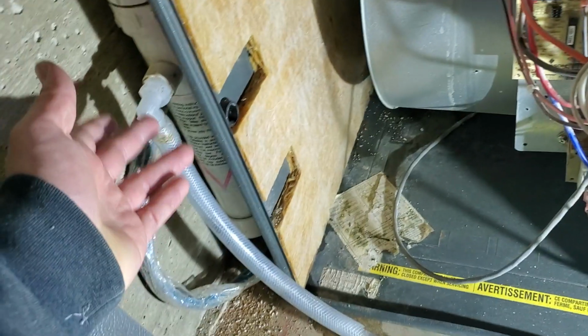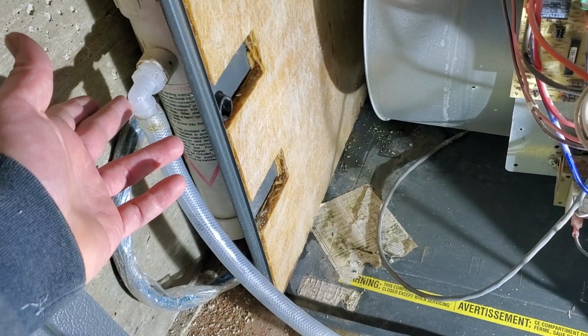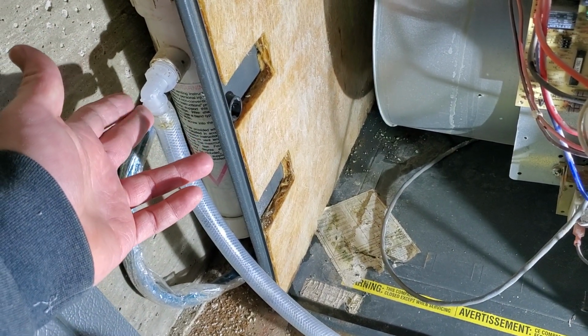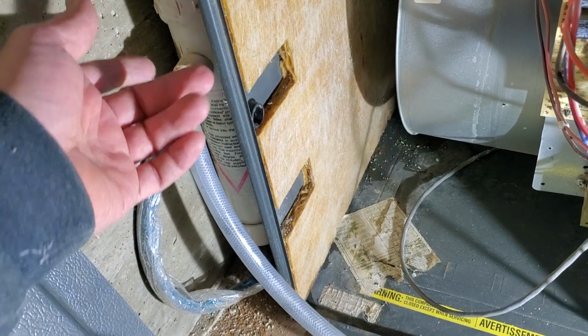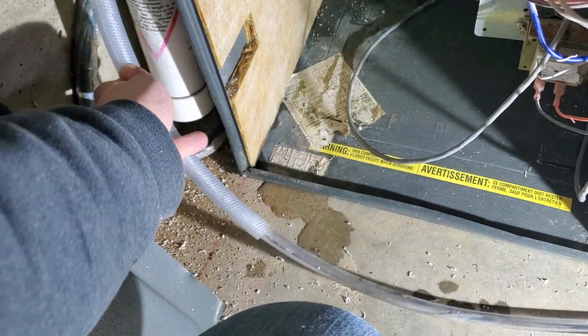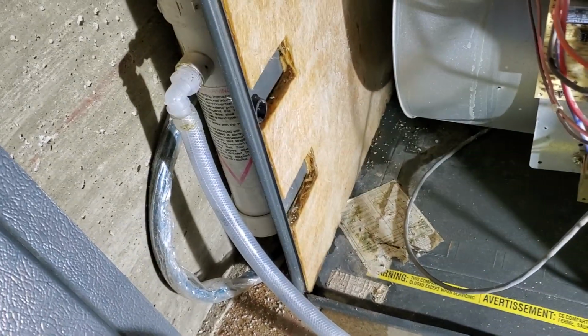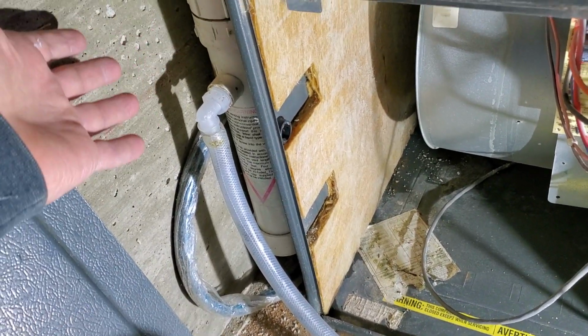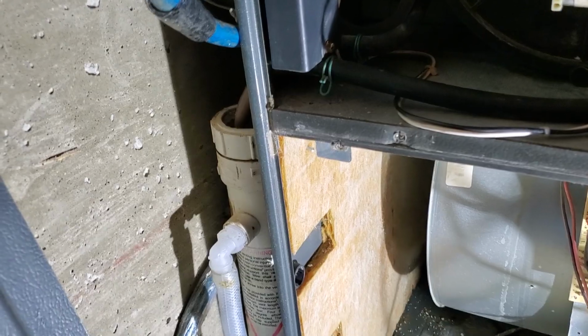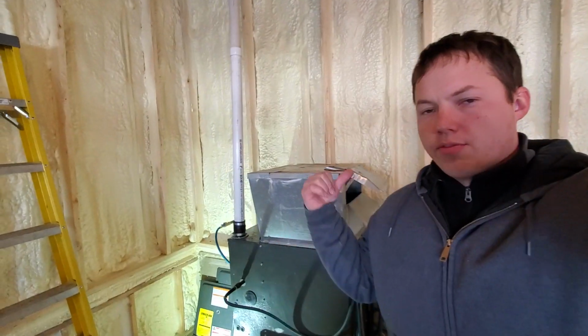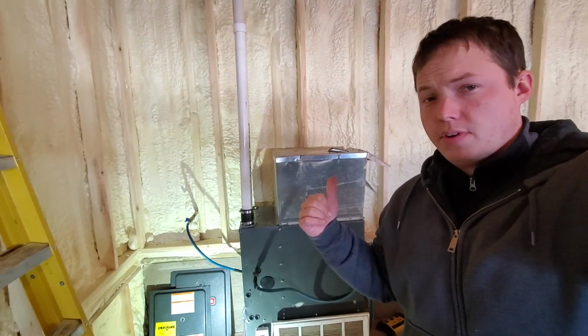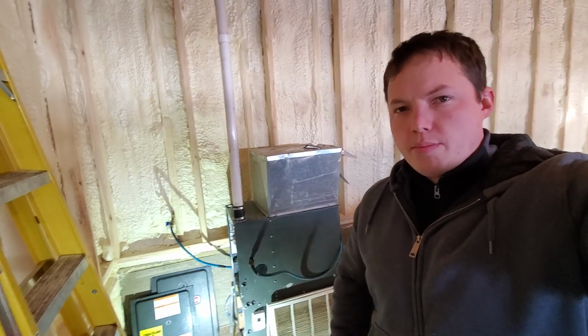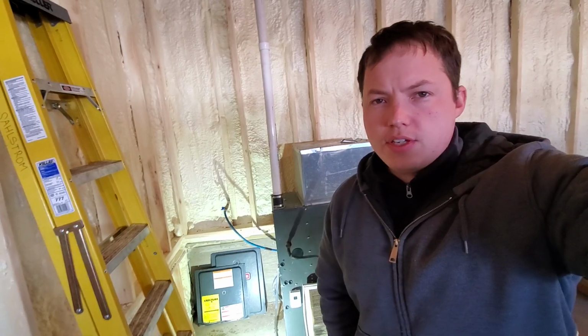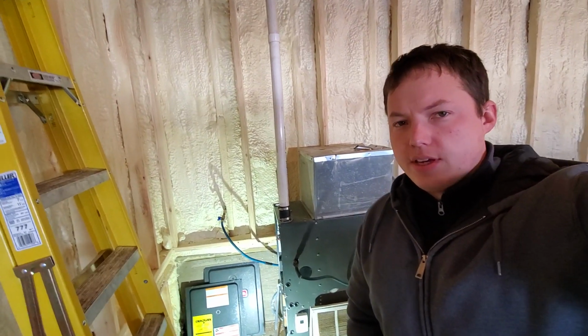So you will have to deal with condensate. You'll have to have a place to catch that. Sometimes if we don't have a drain available, we'll just put like a 5-gallon bucket underneath this, and then we can run the furnace and just empty the bucket once a day, and then you're fine. So that pretty much summarizes what you need to know for getting a temporary high efficiency furnace set up for temporary use, whatever the situation may be that you are facing.